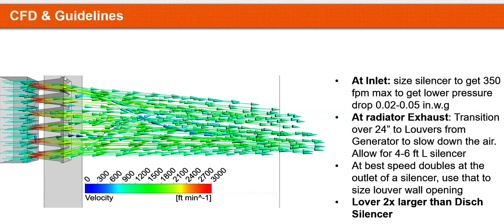Therefore, that transition from the silencer to the louver has to be at least 2 times one of the dimensions of the silencer. So if the silencer is, I want to say, 10 feet wide, your opening at the louver is going to have to be at least 20 feet wide so that you can properly transition, slowing down the air. Otherwise, you're going to ram about 15 to 1800 feet per minute right into the louvers, choking the system, making it so that the generator cannot operate.